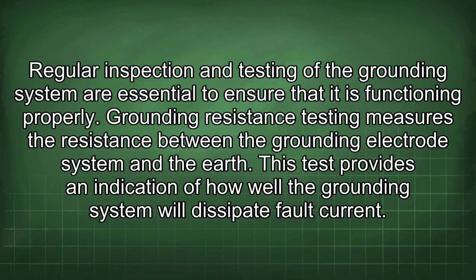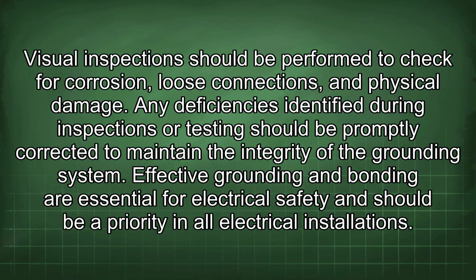Regular inspection and testing of the grounding system are essential to ensure that it is functioning properly. Grounding resistance testing measures the resistance between the grounding electrode system and the earth. This test provides an indication of how well the grounding system will dissipate fault current. Visual inspection should be performed to check for corrosion, loose connections, and physical damage. Any deficiencies identified during inspections or testing should be promptly corrected to maintain the integrity of the grounding system.